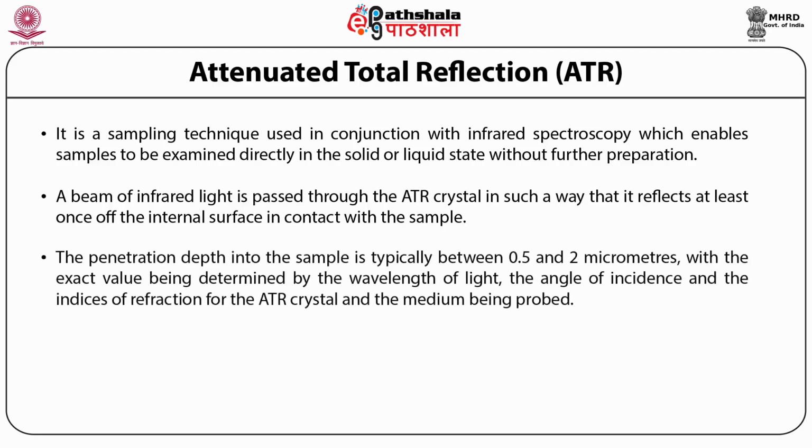The penetration depth into the sample is typically between 0.5 and 2 micrometers, with the exact value being determined by the wavelength of light, the angle of incidence, and the indices of refraction for the ATR crystal and medium being probed. The number of reflections may be varied by varying the angle of incidence. The beam is then collected by a detector as it exits the crystal.